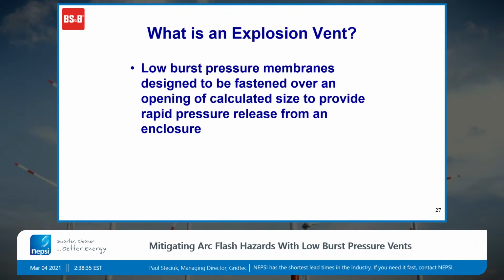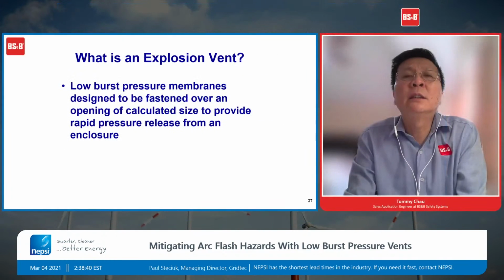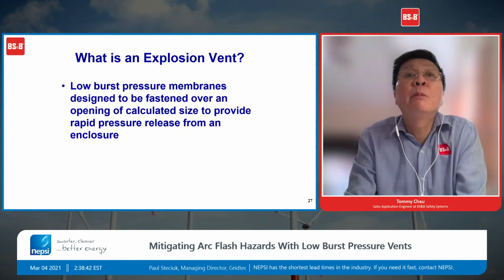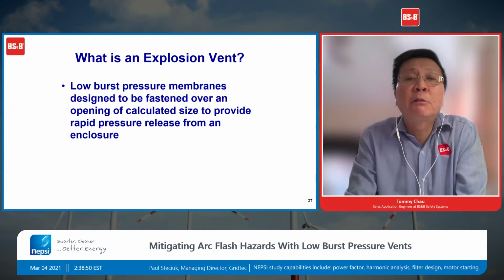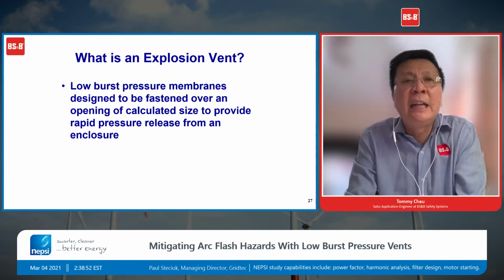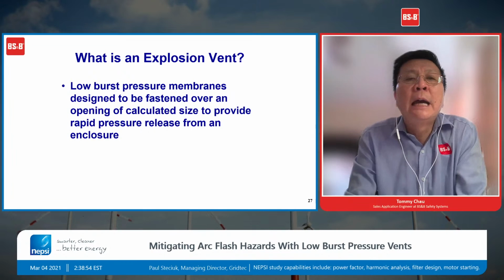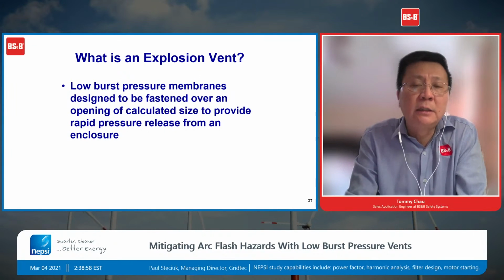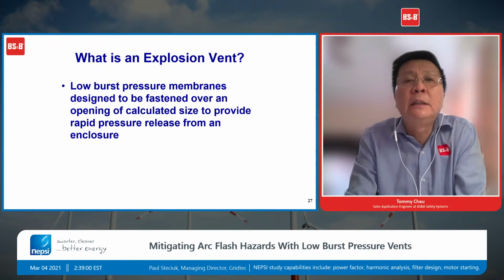So what is an explosion vent? I think we've been talking a bit about this. It is a low burst pressure membrane. It is calculated and designed for an opening. So again, getting back to the calculation per NFPA 68 is how we determine how much explosion venting you need in terms of area, and then we select the sizes for the explosion vent.